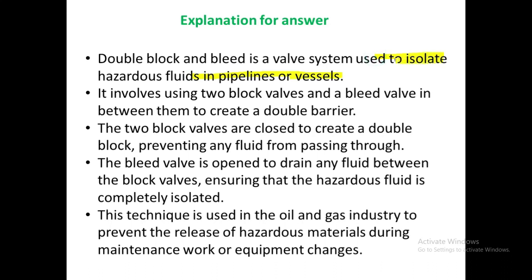It is a lockout concept involving two block valves and a bleed valve — that is why the name 'double block and bleed.' It creates a double barrier and double isolation: two block valves are closed to prevent any fluid from passing through, and a bleed valve is opened to drain any fluid between the block valves, ensuring hazardous fluid is completely isolated.